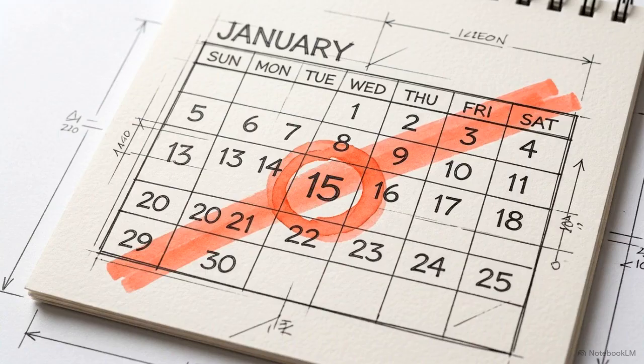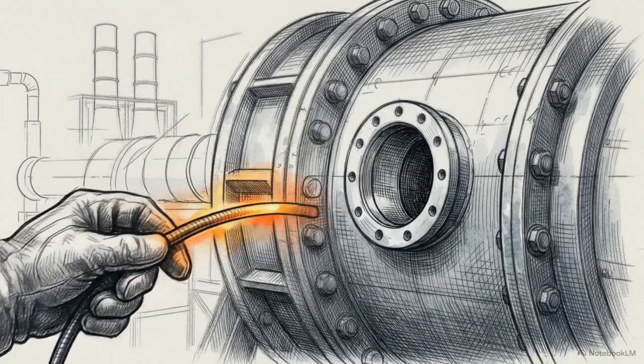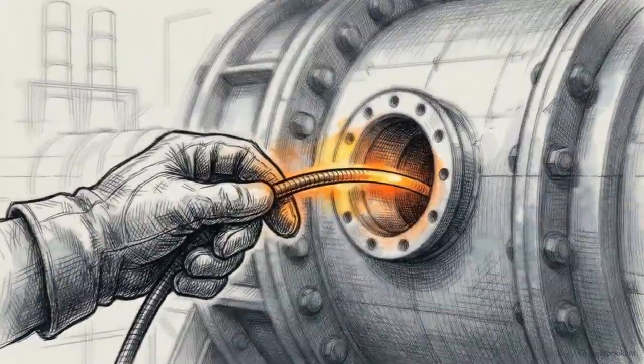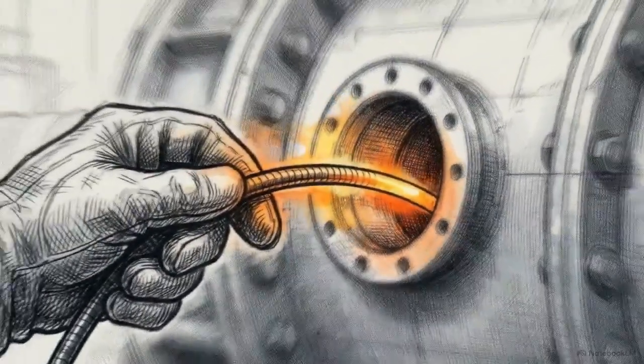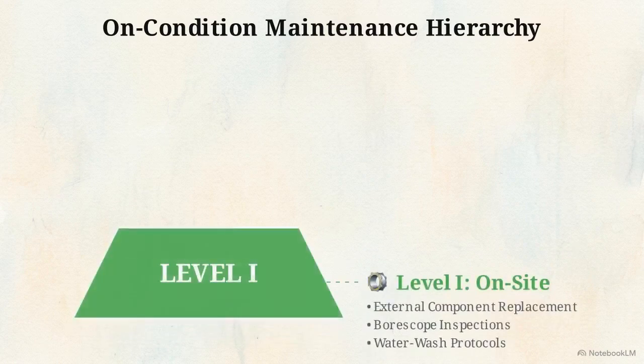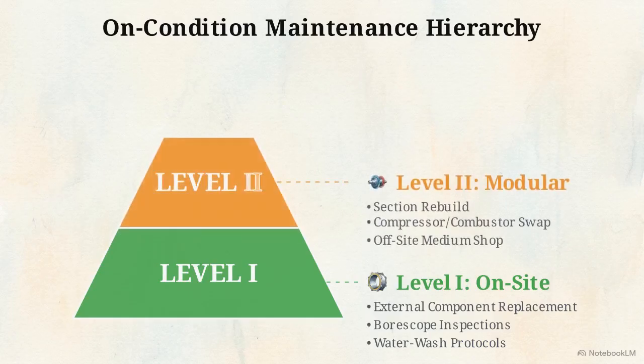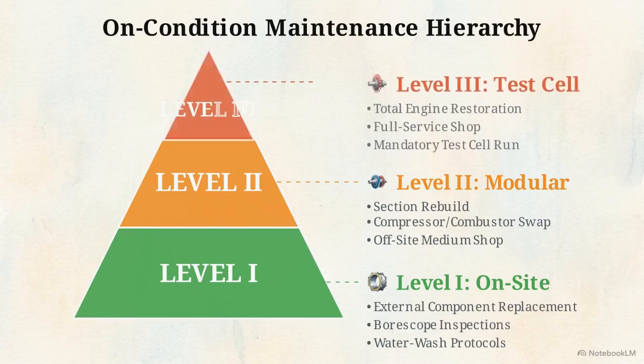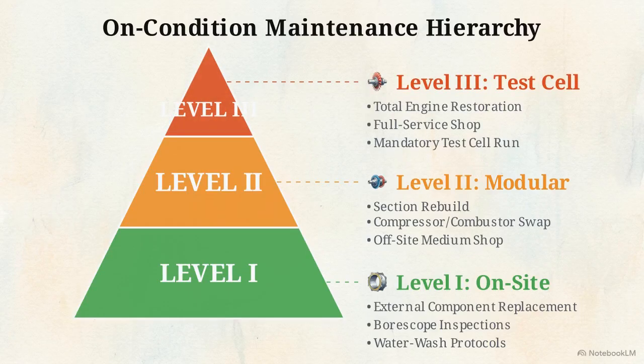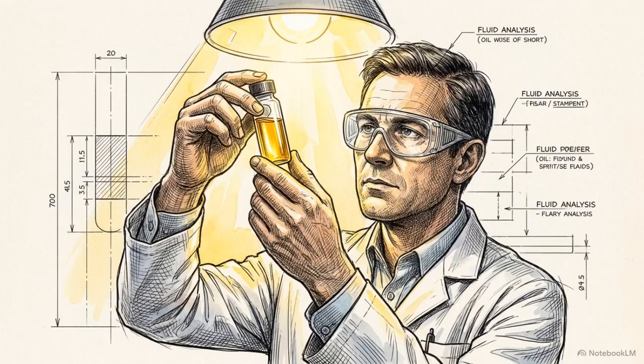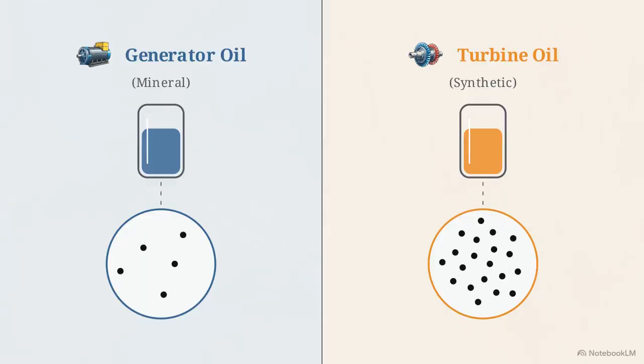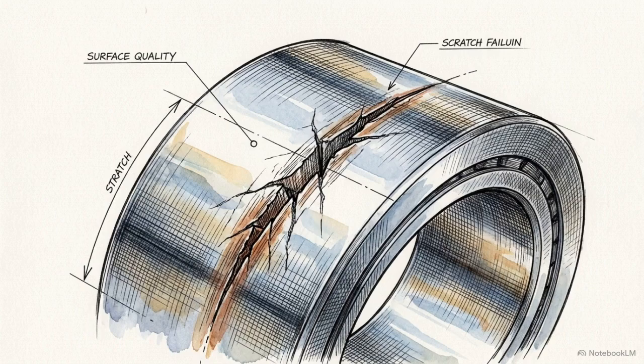Maintaining an aeroderivative turbine requires moving away from fixed calendar-based overhaul schedules. The program runs on on-condition maintenance. Major service is triggered solely by direct physical and diagnostic evidence. This evidence-based system uses a 3-tier hierarchy: Level 1 for on-site visual fixes, Level 2 for modular section rebuilds, and Level 3 for complete restoration in an authorized test cell. Gathering that evidence requires laboratory-grade fluid analysis. Because of their tighter clearances, turbine bearings are held to a much stricter particle count standard than the generator bearings. Contamination invisible to the eye can lead to premature failure.